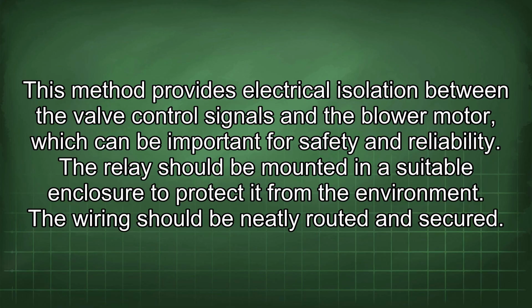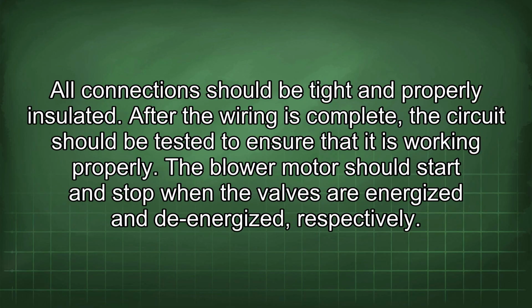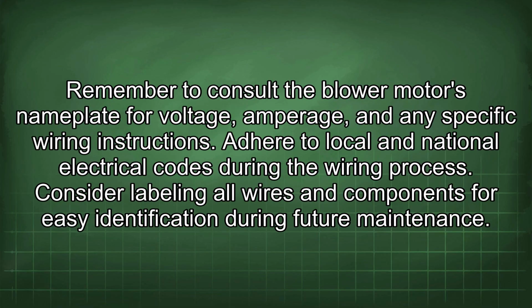The wiring should be neatly routed and secured. All connections should be tight and properly insulated. After the wiring is complete, the circuit should be tested to ensure that it is working properly. The blower motor should start and stop when the valves are energized and de-energized, respectively. Remember to consult the blower motor's nameplate for voltage, amperage, and any specific wiring instructions. Adhere to local and national electrical codes during the wiring process.